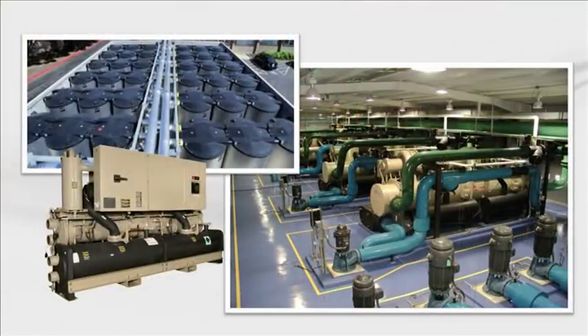Now, let's turn our attention to applications and how they drive chiller plant design. We are seeing chillers being asked to do more than just comfort cooling. More and more designers are looking for more efficient ways to design building HVAC systems. They are utilizing heat recovery, ice storage, cold water storage, free cooling, and other application-driven enhancements to increase the efficiency of chiller plants in the overall building HVAC system. Over the past decade, we have seen an increase in the number of manufacturers who offer these enhanced application chillers. Whether it is air-cooled or water-cooled, these enhancements are no longer considered niche offerings.